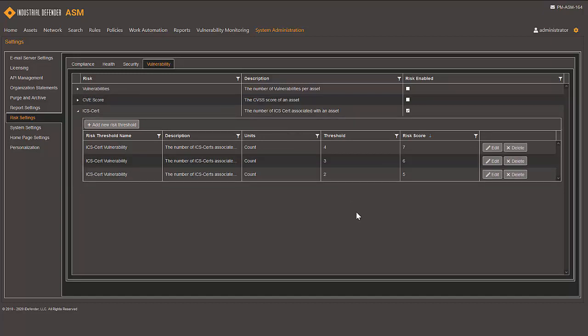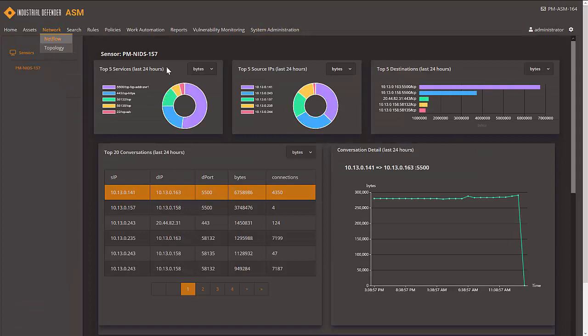Now let's switch gears into our new Netflow application. So Netflow is specifically built on data that flows up from our IDS sensor. This is the sensor that's not only doing IDS, but also responsible for passive monitoring and then assisted passive monitoring, where we actively have the ability to discover assets on the network. So we go out there and do a safe who-is based on the protocol that we're using, whether it be the new BACnet for building management systems, or potentially things like an EtherNet/IP broadcast to determine what's out there.